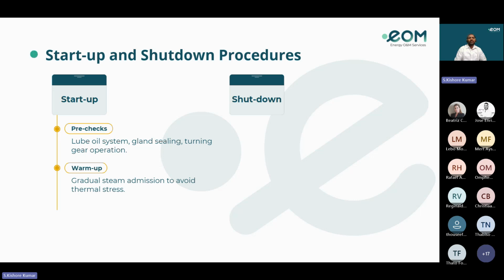In the warm-up, with gradual steam admission, we always have to take care to avoid any thermal stresses in the turbine, because that causes damage to the rotor or some bend in the rotor. It happens because of the differential temperatures. Coming to the rolling and synchronization, the turbine will accelerate to rated speed and be synchronized with the grid or mechanical load.